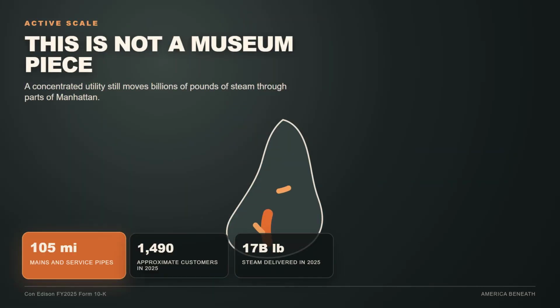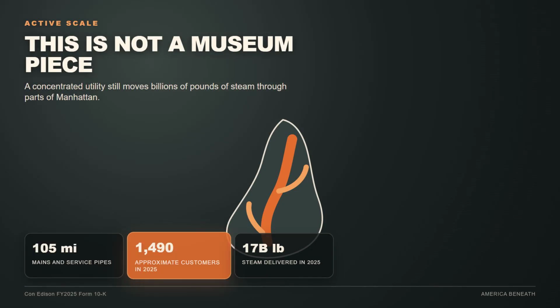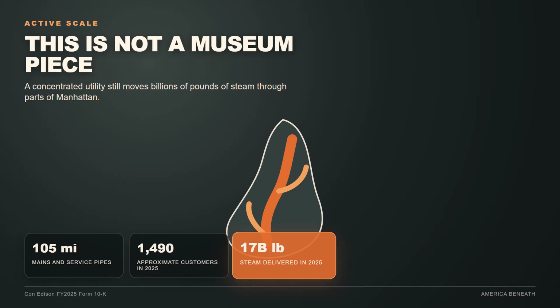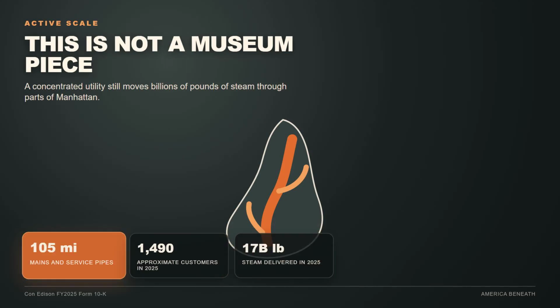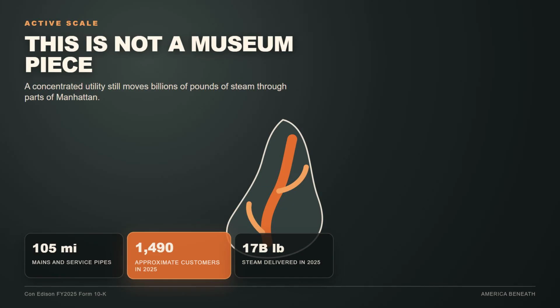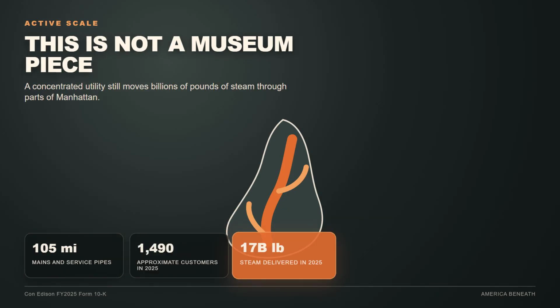The scale changes the story. In its fiscal year 2025 filing, Con Edison described this as the largest steam distribution system in the United States. The company reports roughly 105 miles of mains and service pipes, supported by about 3,000 steam manholes. That is active utility infrastructure, not a preserved industrial exhibit. The same filing says the system delivered about 16,975 million pounds of steam in 2025. Put more naturally, that is nearly 17 billion pounds in 1 year. It went to approximately 1,490 customers in parts of Manhattan.